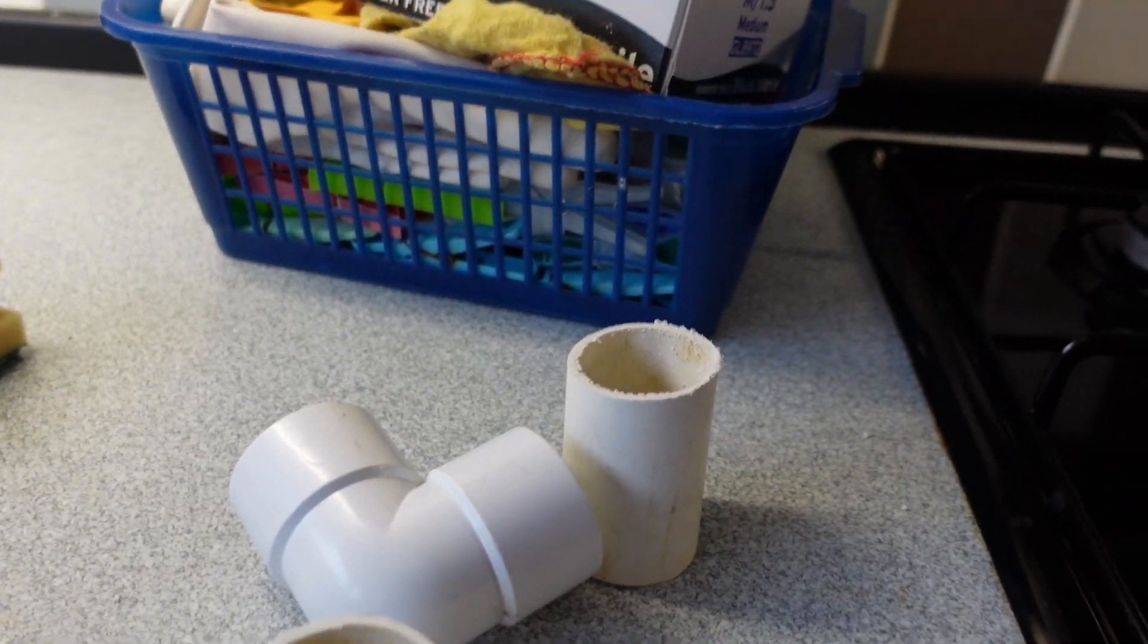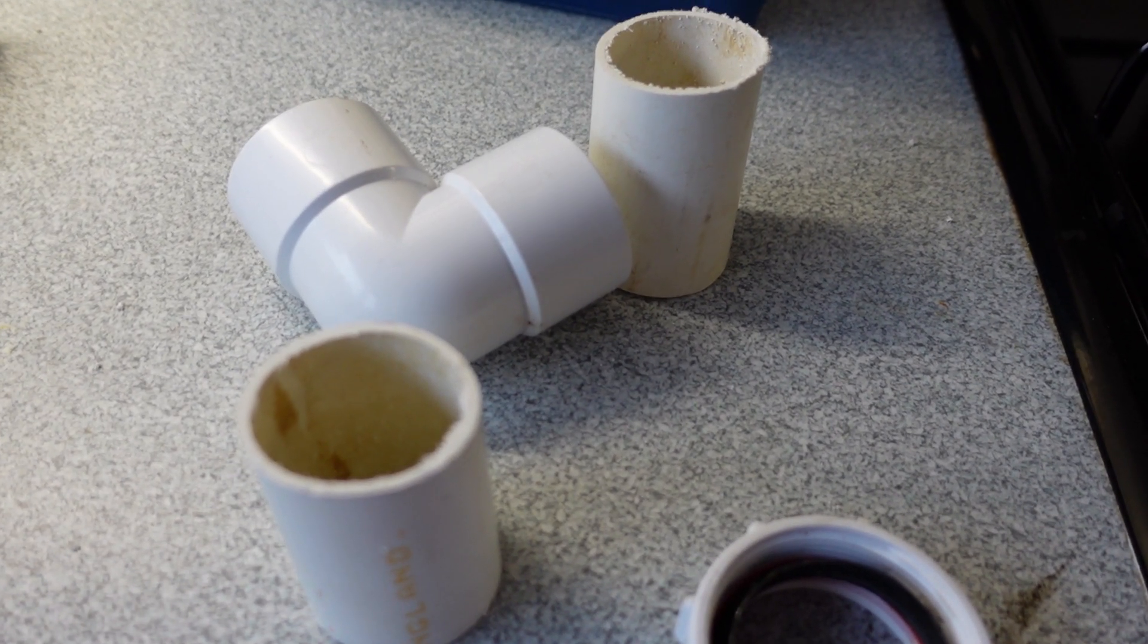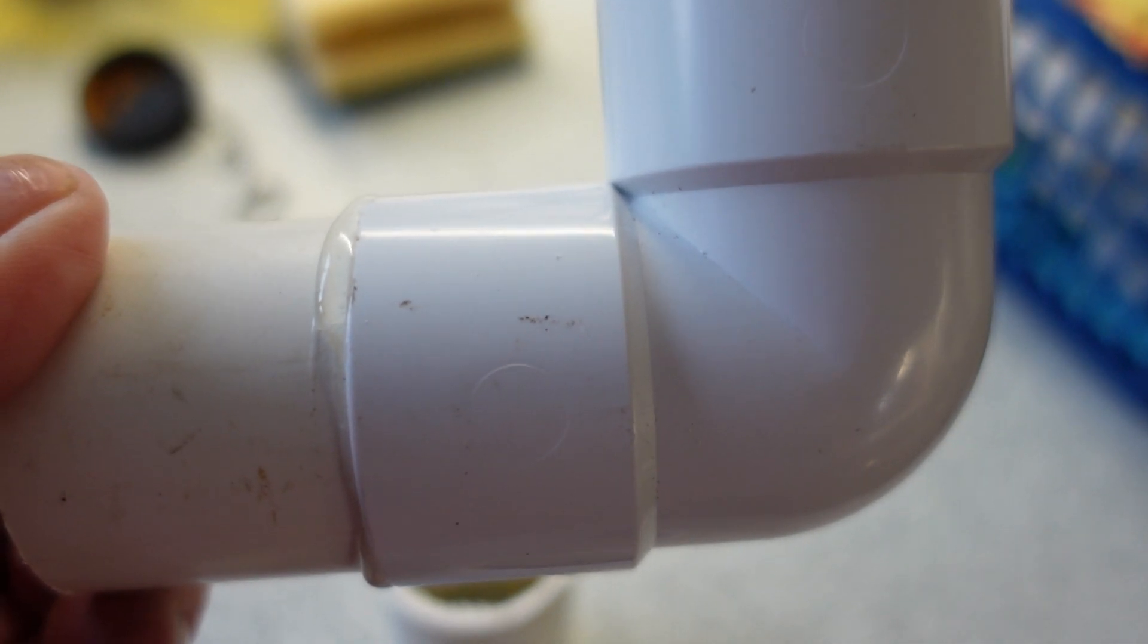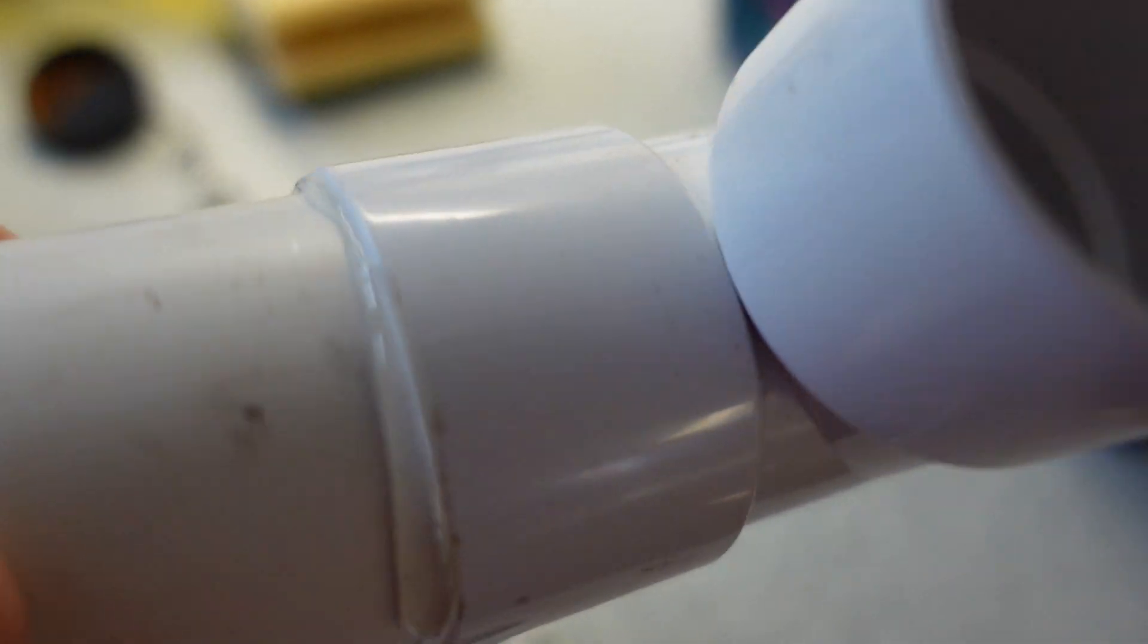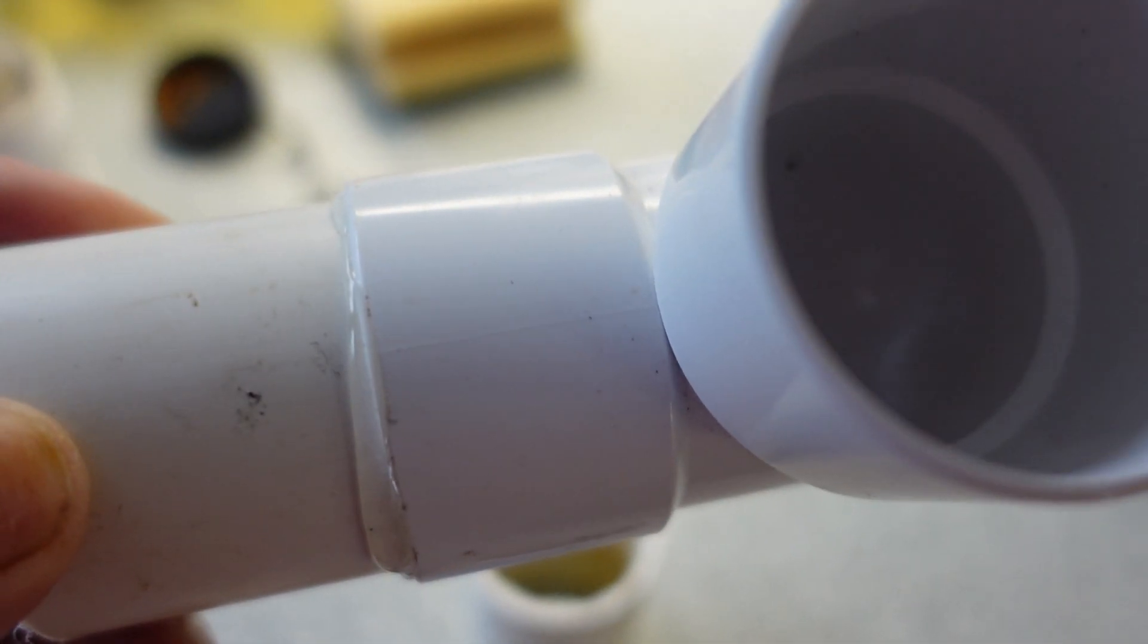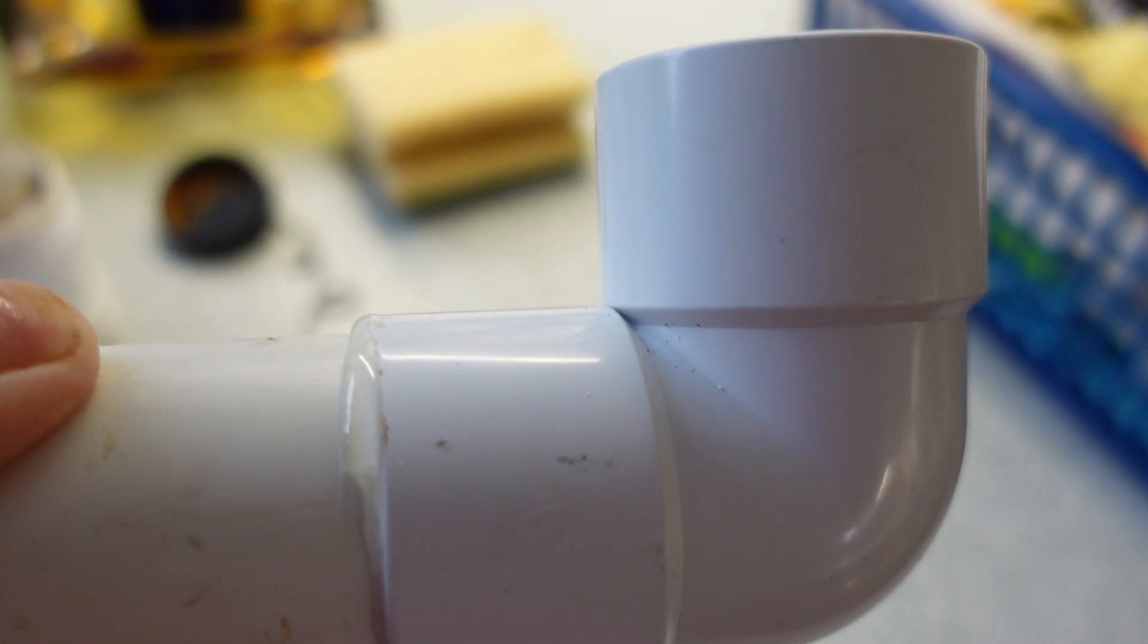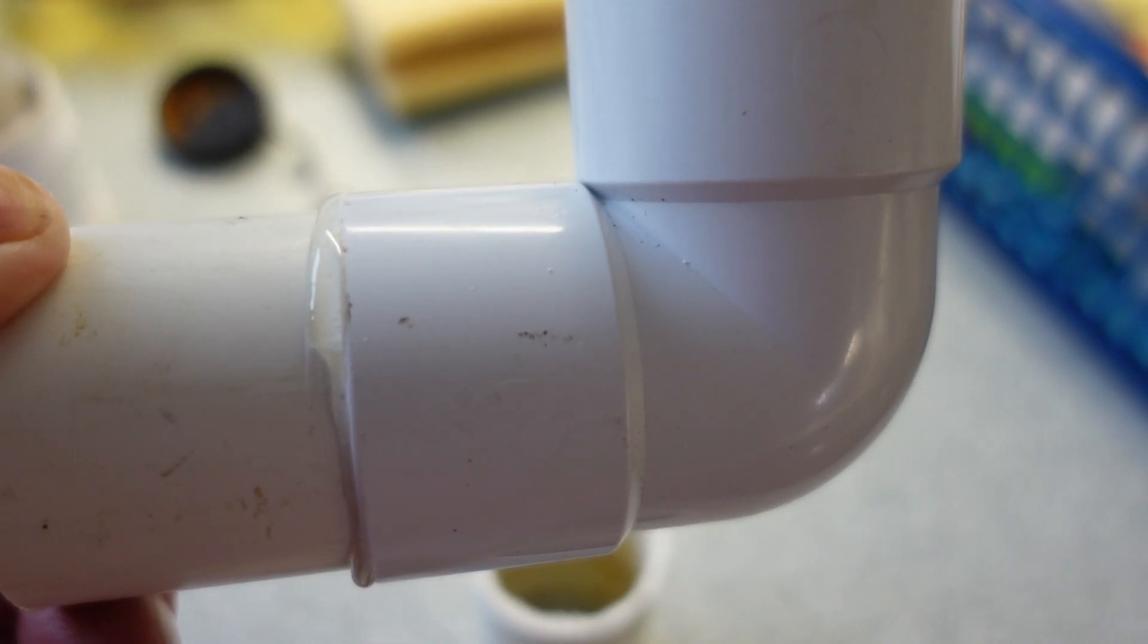Next piece I'm going to make up is this elbow here with these two short bits of pipe. By the way, if you're using these type of elbows, remember they must be solvent welded in. Can't just push them in and hope for the best. Once it is in you won't be able to move it - it's there forever. You get about five to ten seconds once it's pushed in and that's it, gone.